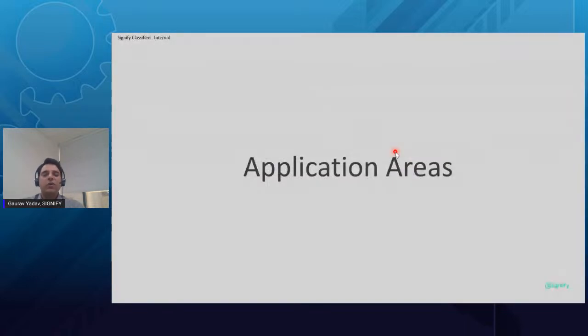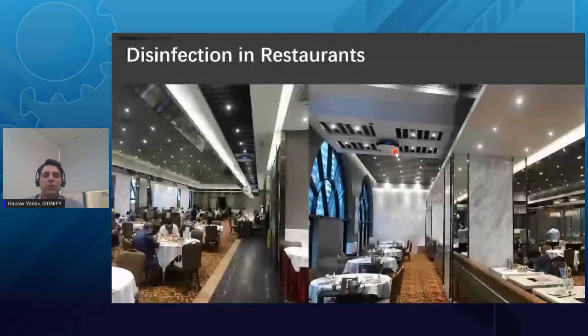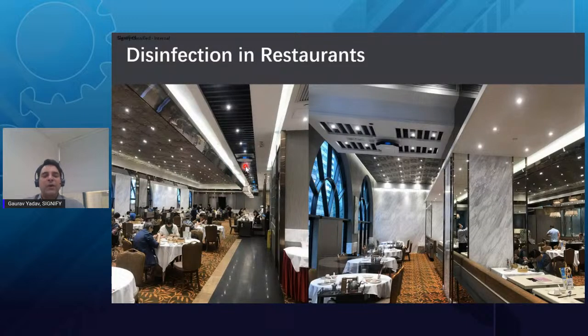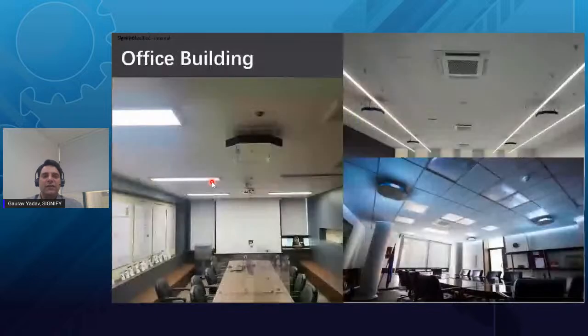Now, I just want to show you some of the application areas and the actual installation. This is how you can do disinfection in restaurants. People are eating around, but if you install a proper upper room UVGI system, with this type of luminaires and products in place, people can eat and walk around freely, because the UVC zone will be created on top of the room. So it is absolutely safe when people are around. You just need to follow the safety guidelines. This is how it can be installed inside the office.